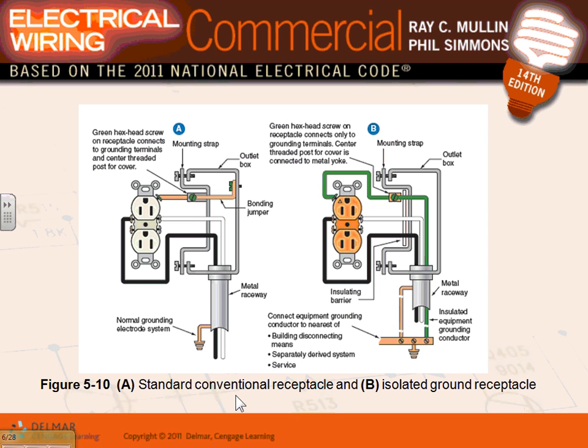Okay, here's an isolated ground receptacle. First, the receptacle has to be designed as an isolated ground receptacle. Basically, the grounding slot here, the bottom, is completely isolated from the metal frame of the receptacle.